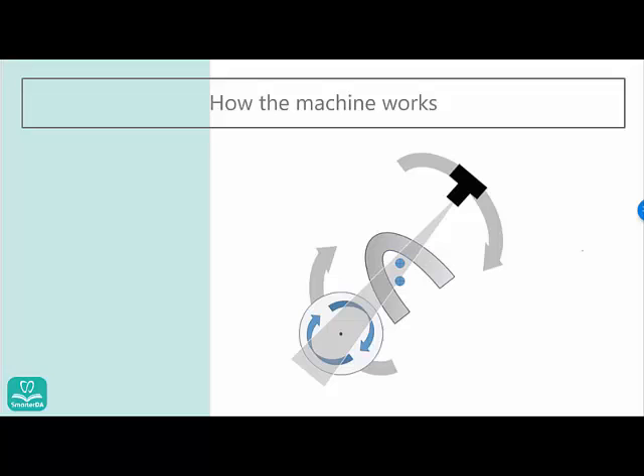The machine works by having a tube head — the camera — rotating around the patient, while the film or receptor goes around the dental arch. The focal trough is very narrow, meaning if you move just one to three millimeters forward or backward, the image is out of alignment. You need to be exactly in the designated area, and that's the challenge because patients want to move and don't know where to put their tongue or their chin.